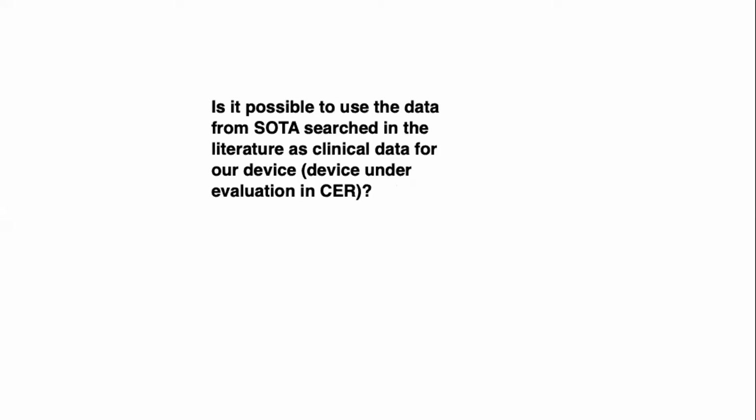So no, state-of-the-art data that's used to establish safety and performance acceptance criteria, ranges, upper and lower bounds, must not be your own clinical device data alone. It must be from competitors or pooled or mixed data or from systematic reviews.